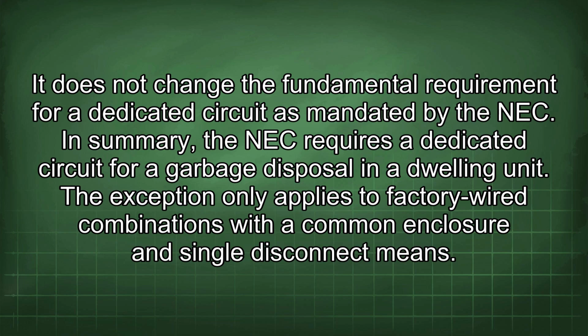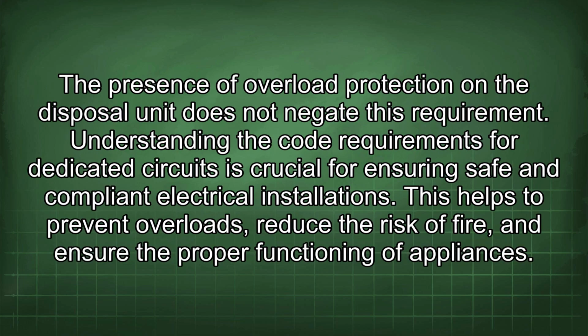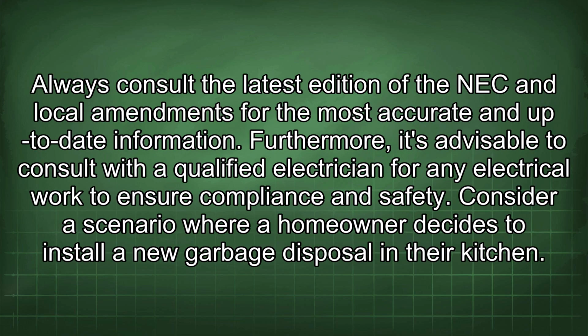In summary, the NEC requires a dedicated circuit for a garbage disposal in a dwelling unit. The exception only applies to factory wired combinations with a common enclosure and single disconnect means. The presence of overload protection on the disposal unit does not negate this requirement. Understanding the code requirements for dedicated circuits is crucial for ensuring safe and compliant electrical installations. This helps to prevent overloads, reduce the risk of fire, and ensure the proper functioning of appliances. Always consult the latest edition of the NEC and local amendments for the most accurate and up-to-date information. Furthermore, it's advisable to consult with a qualified electrician for any electrical work to ensure compliance and safety.